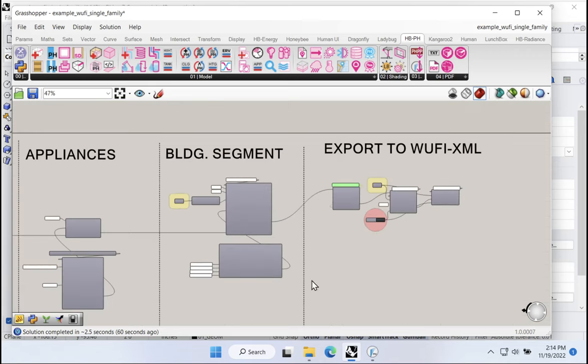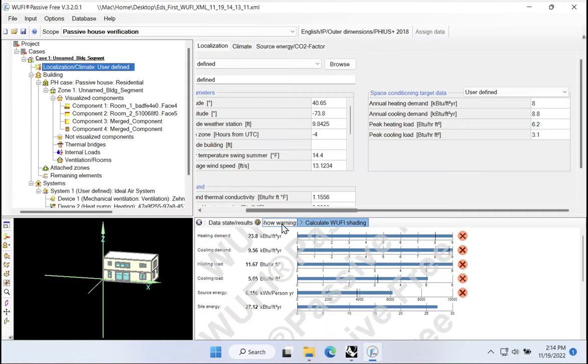Our model is now set up with the right threshold values in. Now we know that we are way over our thresholds. If our heating energy demand target is 8 kBTU per square foot per year, we currently show 23.8. If our cooling energy demand is limited to 8.8 kBTU per square foot per year, we currently show 9.5 to 9.6. We're way over the thresholds on both heating and cooling, and of course on kilowatt hours per person per year of source energy as well. When we come back in future videos, we'll turn our attention to that and see what we need to do in order to improve the overall energy performance of our building.